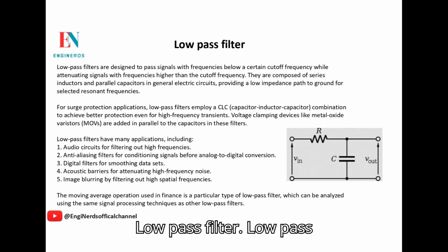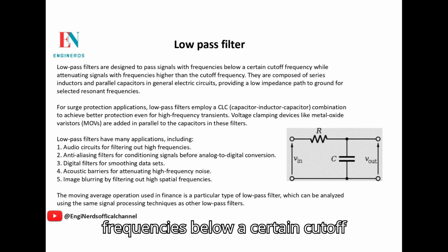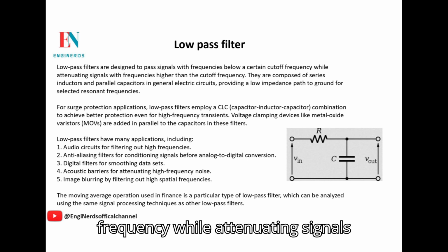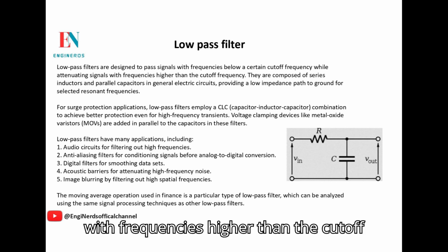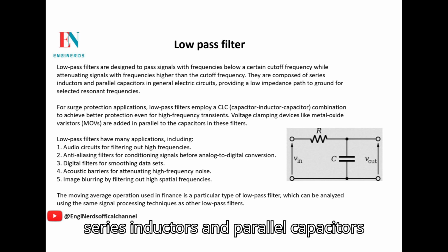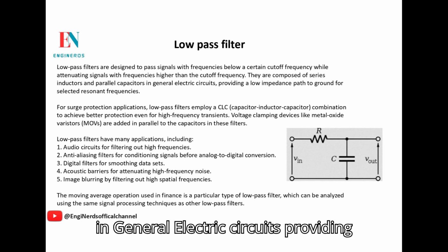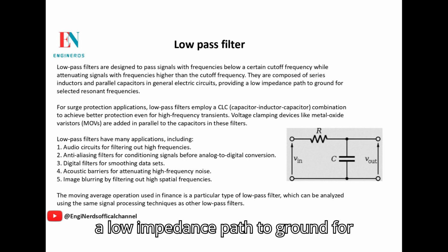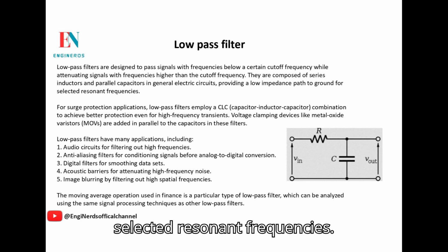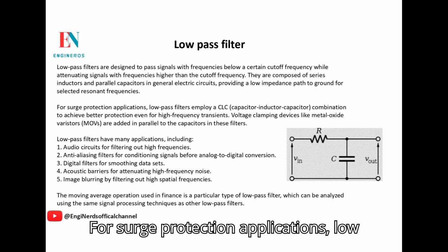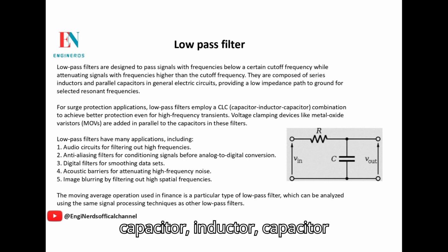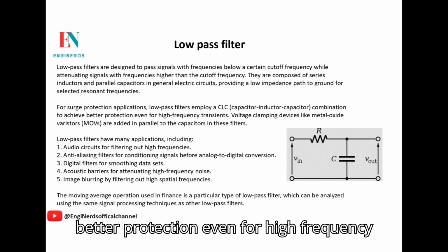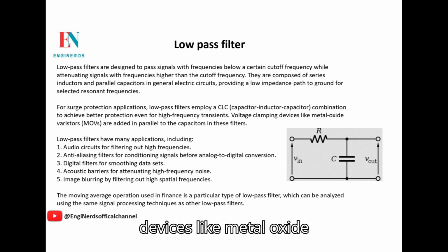Low-pass filter. Low-pass filters are designed to pass signals with frequencies below a certain cutoff frequency while attenuating signals with frequencies higher than the cutoff frequency. They are composed of series inductors and parallel capacitors in general electric circuits, providing a low impedance path to ground for selected resonant frequencies. For surge protection applications, low-pass filters employ a CLC, capacitor-inductor-capacitor, combination to achieve better protection even for high-frequency transients. Voltage clamping devices like metal oxide varistors, MOVs, are added in parallel to the capacitors in these filters.